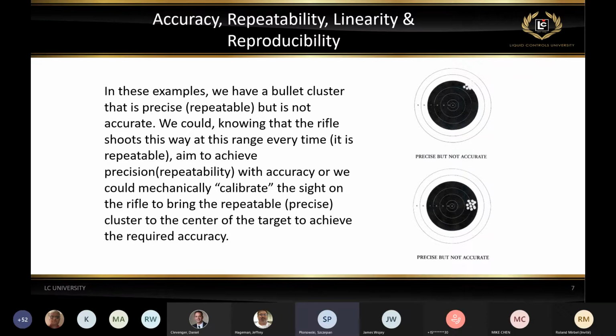Meters coming out of the factory are tested. We know they meet the standards they're designed to meet. But in the field, they will be operating in different conditions with different pump systems, different valves, different liquids. What we're looking for in a meter in general is repeatability. Repeatability is a precondition for a meter to be accurate. Because if we look at those clusters of precise shots, all we have to do is take those clusters and shift them over to the center, which will provide us with not only a repeatable, but also an accurate unit.